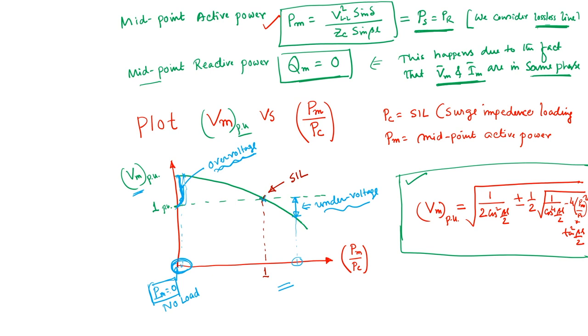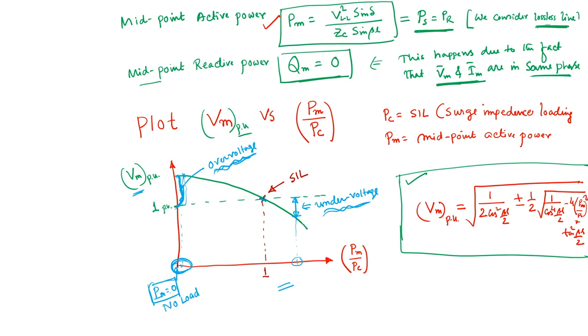Both undervoltage and overvoltage require mitigation through compensators. Compensators not only handle steady-state over/undervoltage but also help during dynamic loading and contingency conditions. The primary goal in steady state is to mitigate overvoltage under light loading and undervoltage under rated loading conditions.